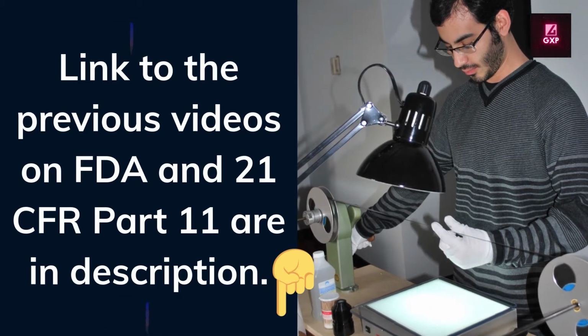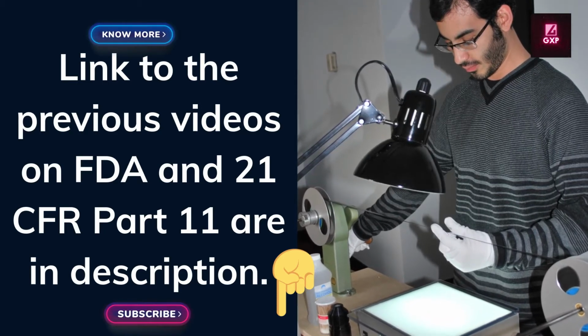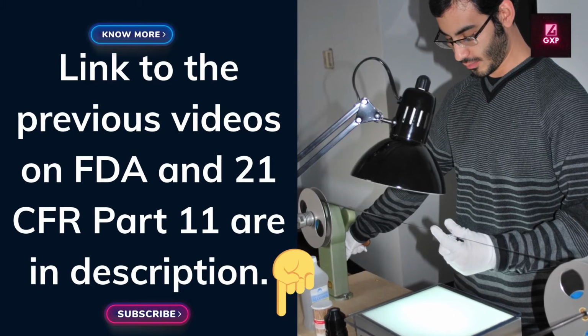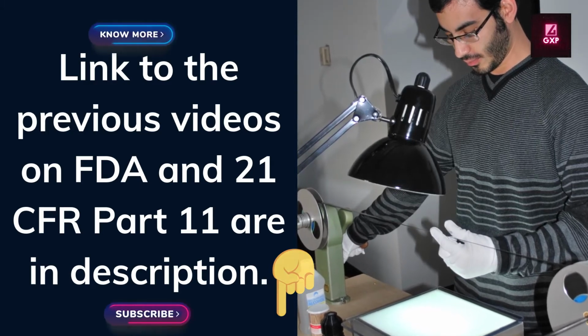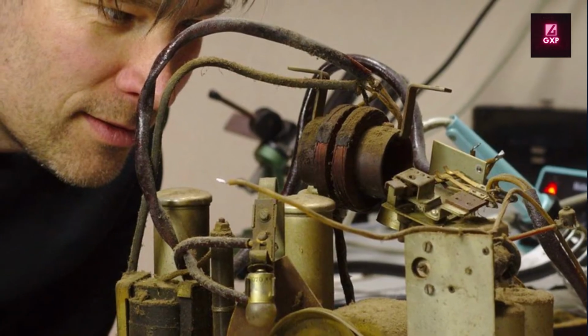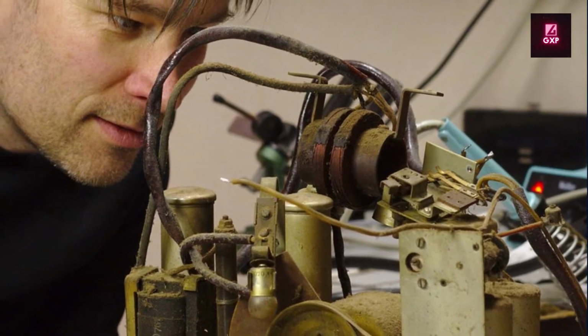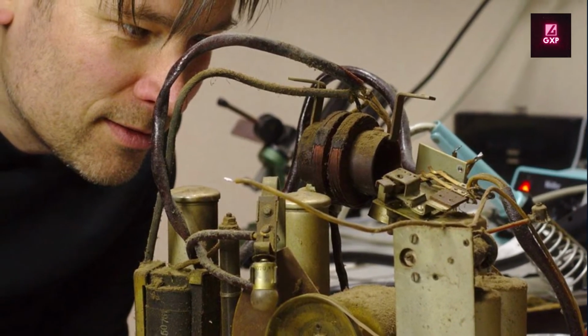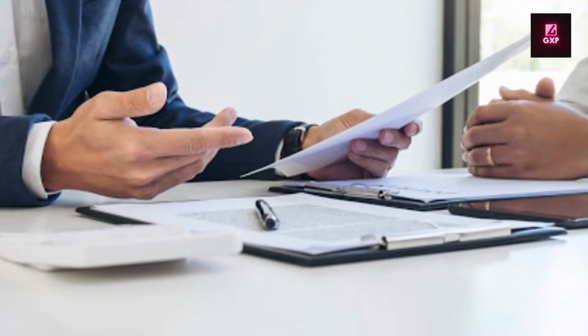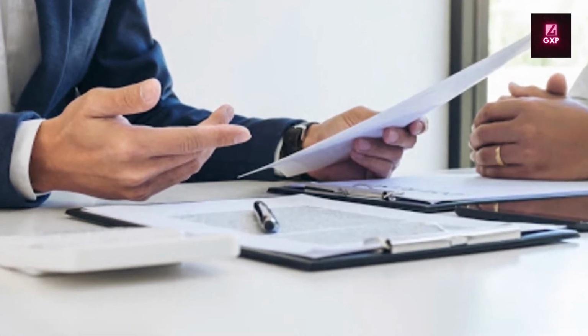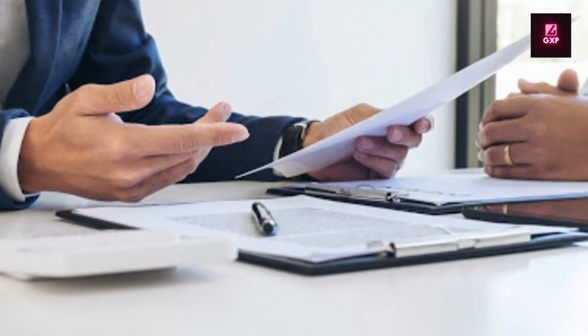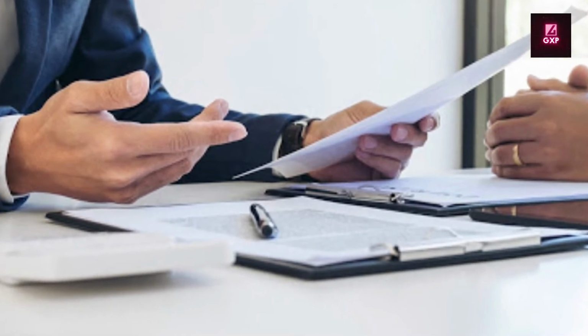FDA Form 484, Receipt of Samples. During the inspection, if FDA inspectors want to take any sample, they have to issue a receipt of those samples on Form 484. It has the quantity of sample with the lot number of the product sampled.